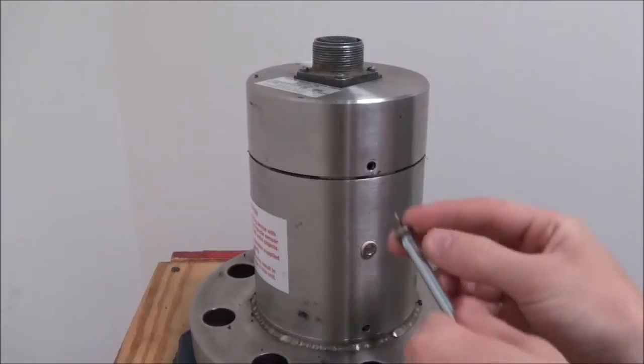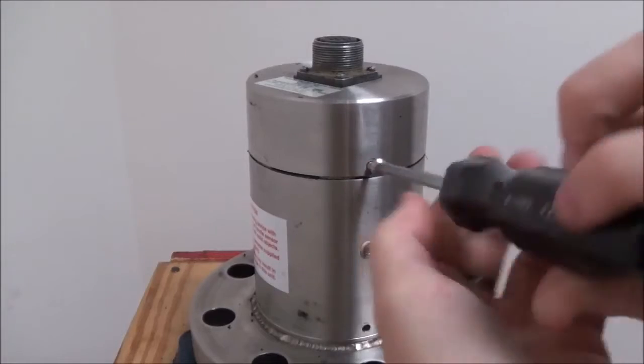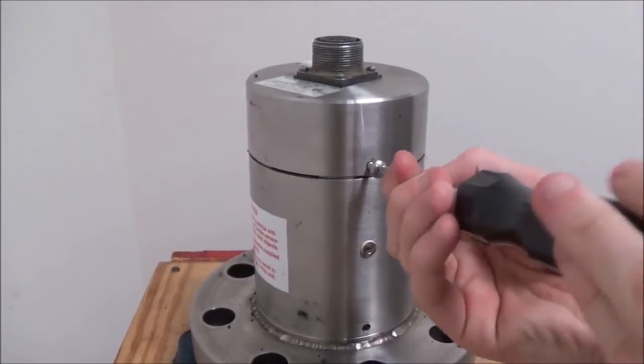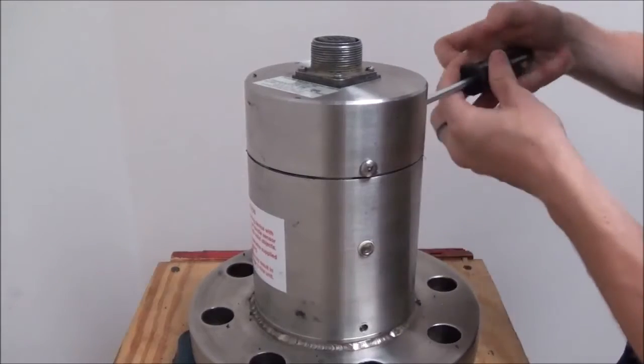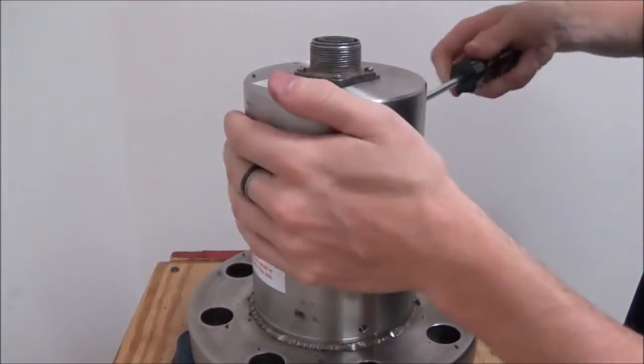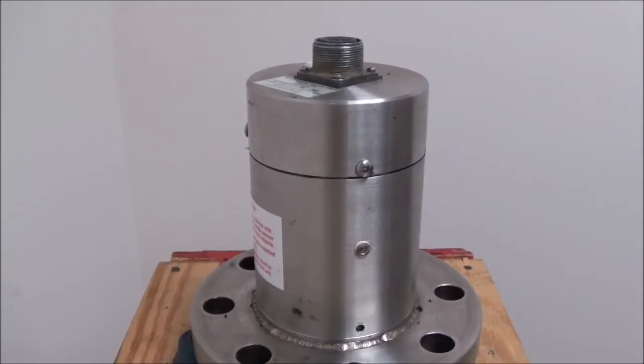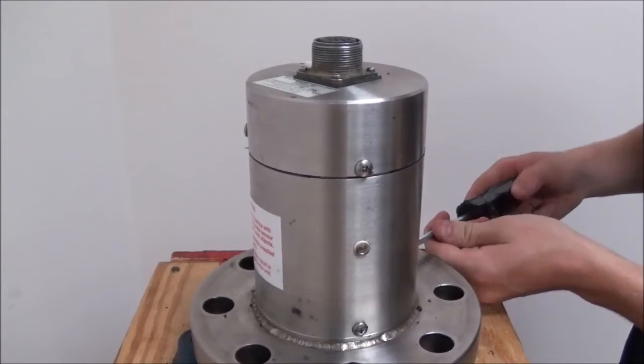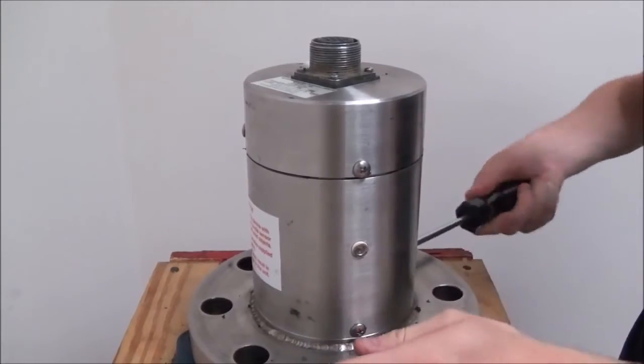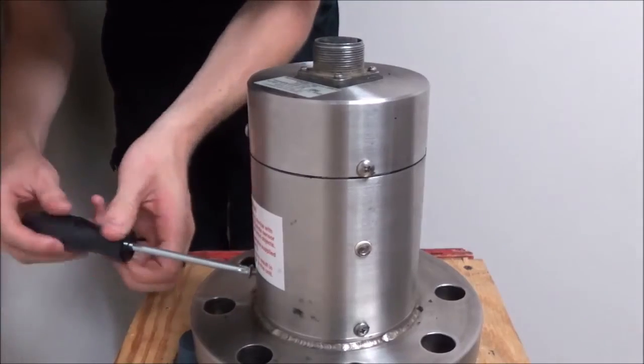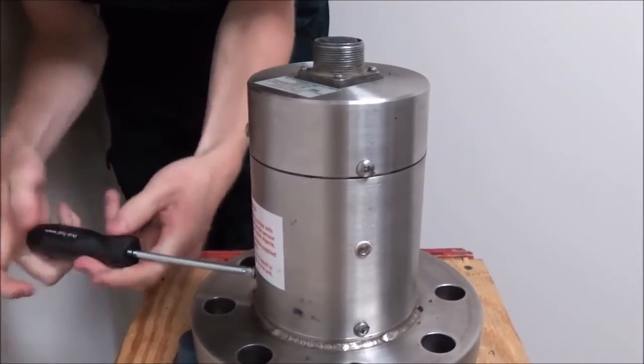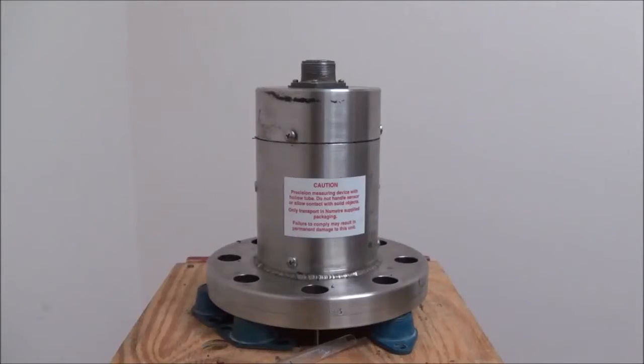All there is left to do now is to re-screw all 6 screws into the transducer block cover and the sensor block cover. And there you have it. You have successfully added the block RTD to your Nametre viscometer.